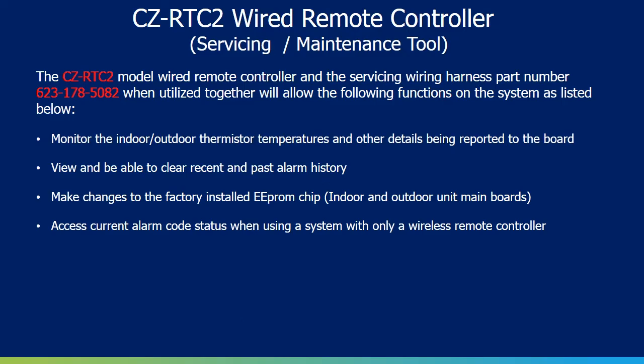The CZ-RTC2 wired remote controller, when used along with the wiring harness part number 623-178-5082, can be utilized as a service maintenance tool. This allows the servicer to monitor both the indoor and outdoor unit thermistor temperatures, along with other details being reported back to the board.